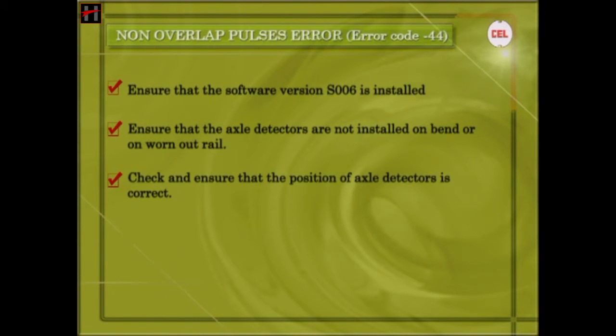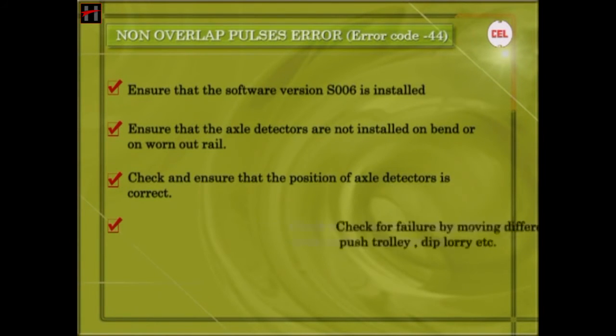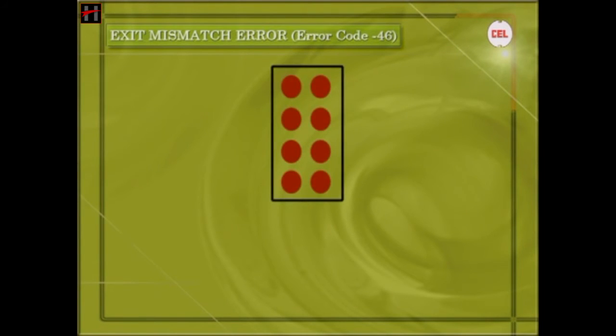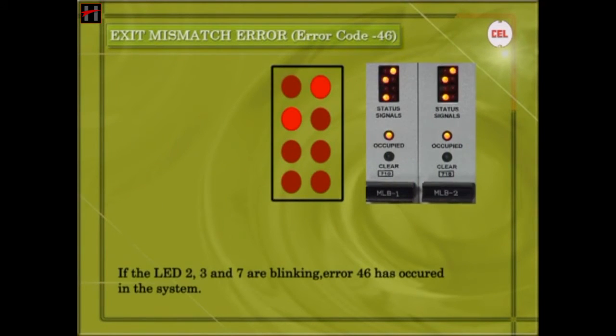Check and ensure that the position of the axle detectors is correct. Check for failure by moving different types of trolleys — motor trolley, perforated push trolley, dip lorry, etc. Exit Mismatch Error: If LEDs 2, 3, and 7 are blinking, then Error 46 has occurred in the system.